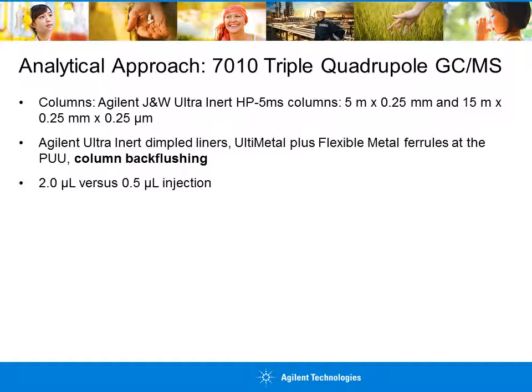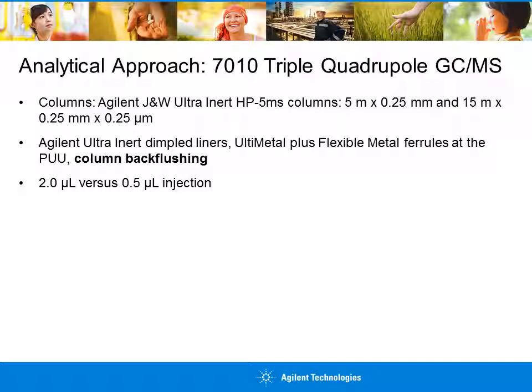As mentioned earlier, QuEChERS sample preparation allows for the extraction of compounds from complex matrices, but does not exhaustively remove all contaminants. Hence, backflushing the GC columns ensures that high-boiling compounds in the matrix are not passed through the column, reduces column bleed, eliminates ghost peaks, and minimizes contamination of the mass spectrometer. This technique, coupled with the ultra-efficient ionization source in the 7010 triple quadrupole GC-MS/MS, allows for smaller injection volumes while still achieving high sensitivity of target analytes.